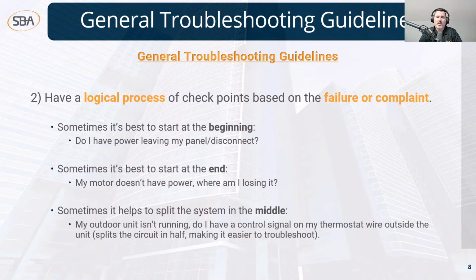In this example, maybe you have a split system. You go to your outdoor unit and it's not running. Check to see if you've got a control signal calling for it from your thermostat wire—you've just split the circuit in half. If you've got power there telling it, maybe you've got power on the Y, which should be bringing on your contactor, but nothing's running. If you have power on Y, you don't need to go backwards toward the equipment to check anything—you know your problem is isolated to that outdoor equipment because it's getting the signal; it's just not doing its thing inside.